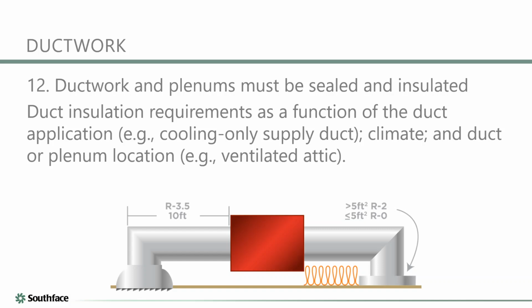Well, and that's part of it too, because on one hand, the condensate issue you'll find more where the duct is inside the building and inside the cooling space, so to speak, right? And on the energy lost issue, you'll find it more in the attic. If it's leaking, you're losing 20-30% of your conditioned air just going to wherever, right? And either way, it's not going to benefit the building. So yes, insulation is extremely important with an HVAC ducting system. And I think our footnote here is it sounds really easy to say you have to seal your plenums and your ductwork. There's a lot of connections and joints and seams and takeoffs that actually go into doing that correctly. And it probably doesn't get as much focus as it might deserve.